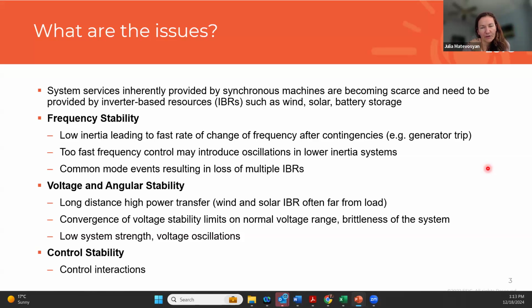Previously there was a very clear signal that the system is leaning towards voltage instability and that you're getting close to the voltage stability margin. Whereas now it may look like normal operating conditions, and then a very small change on the grid may lead to voltage collapse. The term sometimes used is that the system is becoming more brittle, so it takes longer to get to instability, but once it happens, it's very abrupt and hard to contain.